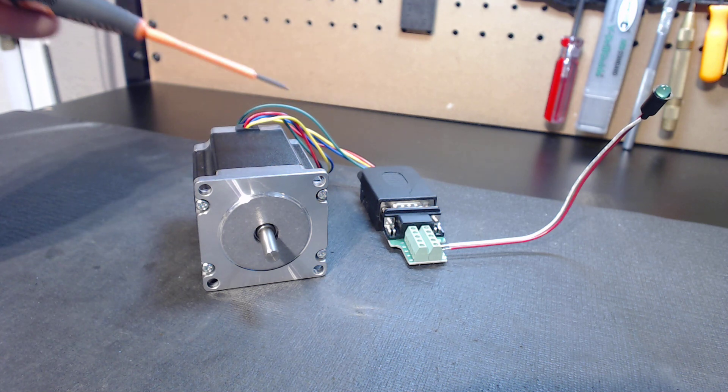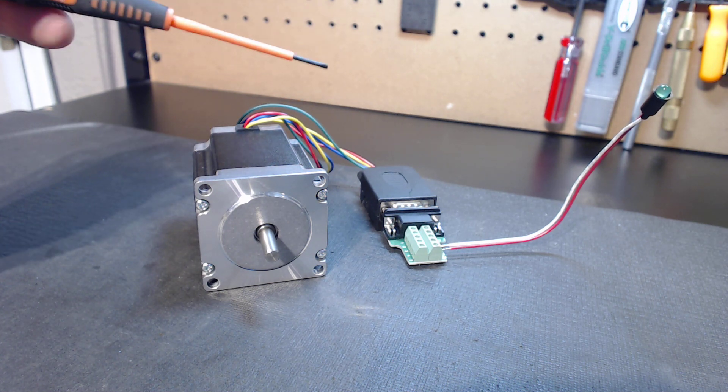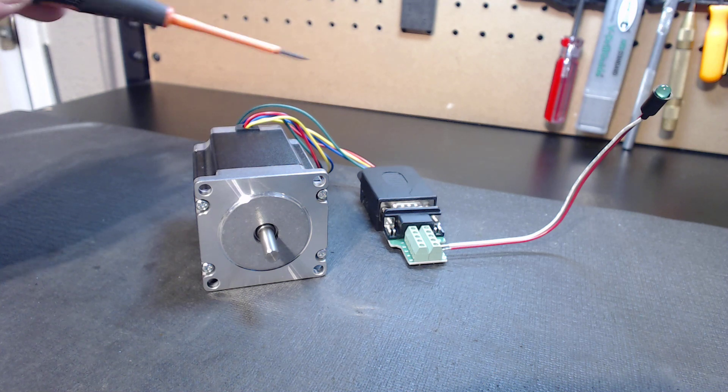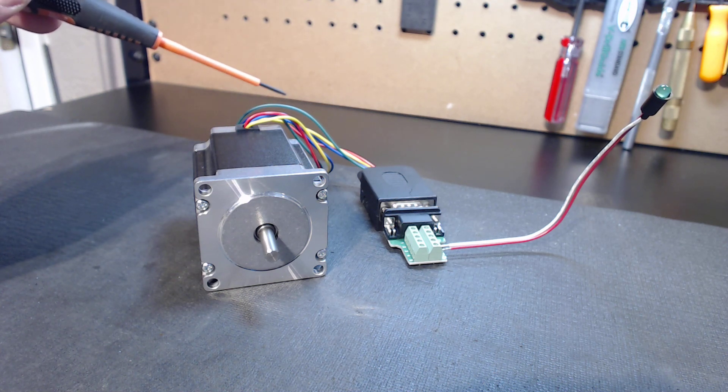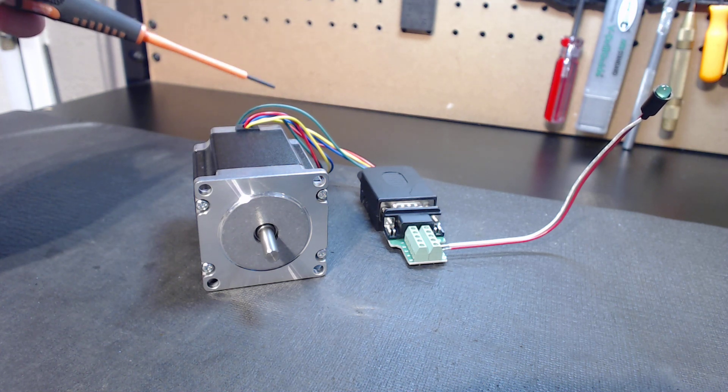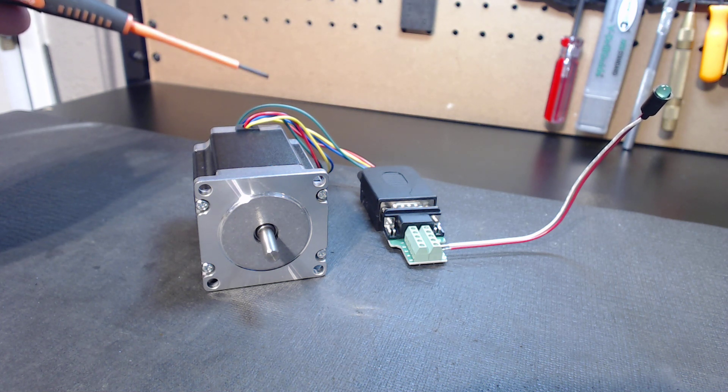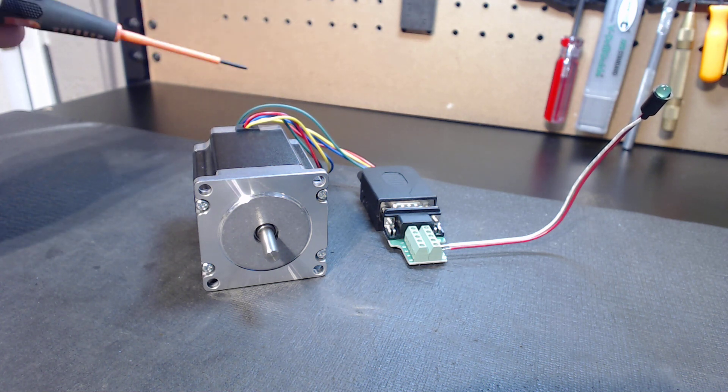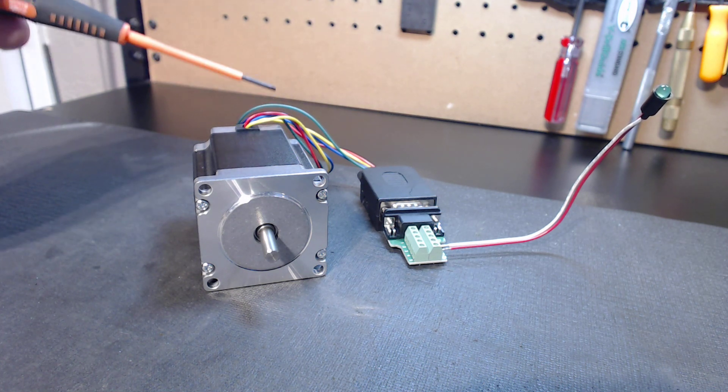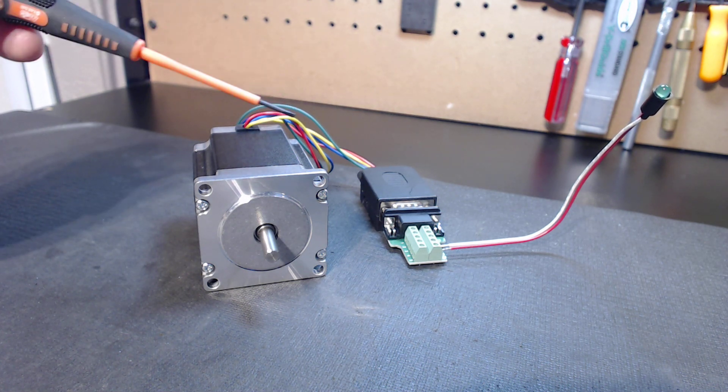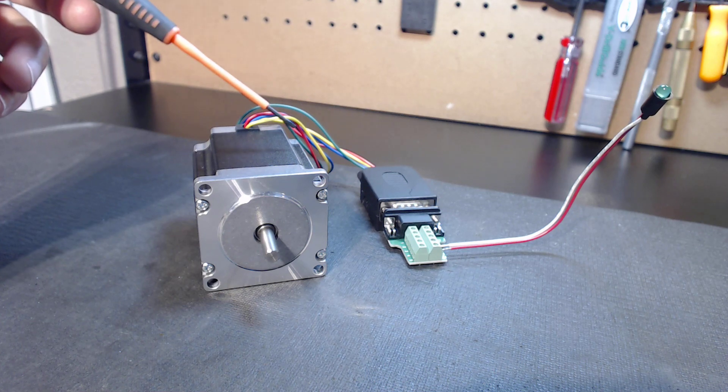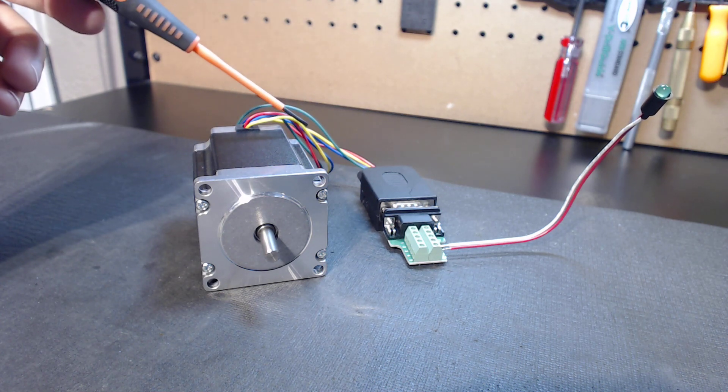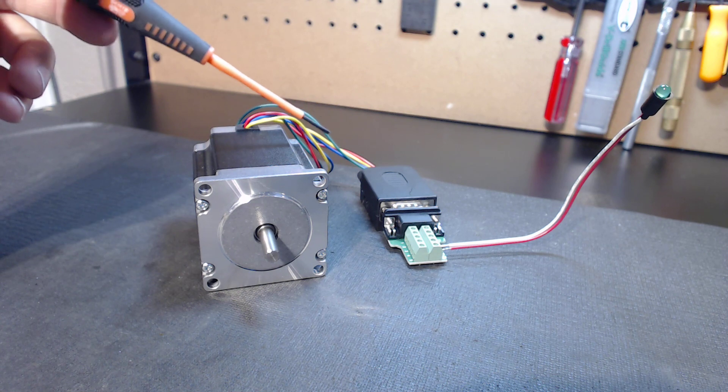Unipolar is a six-lead motor. You may have one of those. Six-lead motors have the center taps and then you have eight-lead which is really ridiculous. Keep in mind eight-lead you're typically going to have two leads that go together to make one of the leads. So you're actually taking the eight leads and turning them into four leads because you're binding two together to convert it into a bipolar motor. Most drives on the market don't support an eight-lead motor. It'll be a bipolar format hookup.